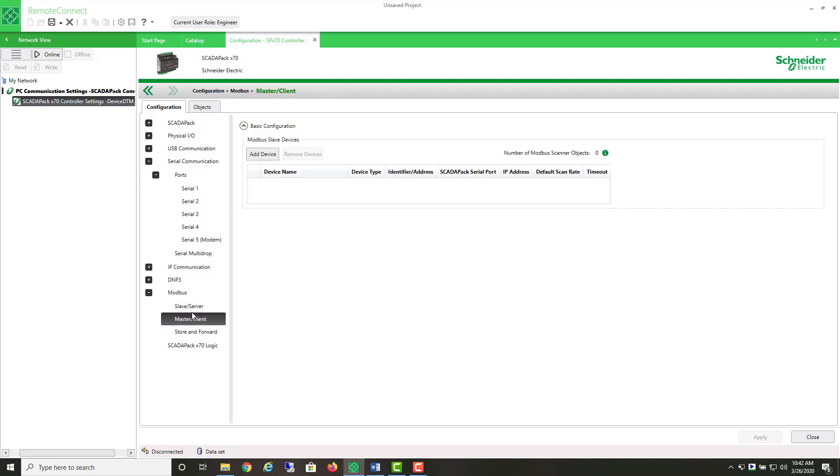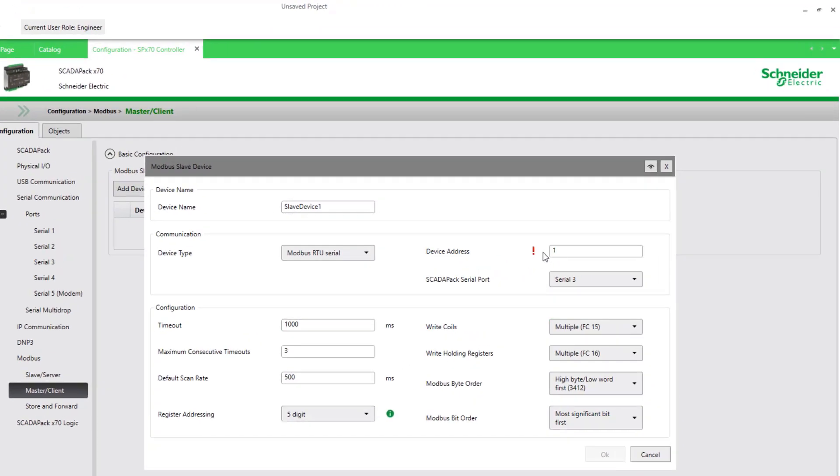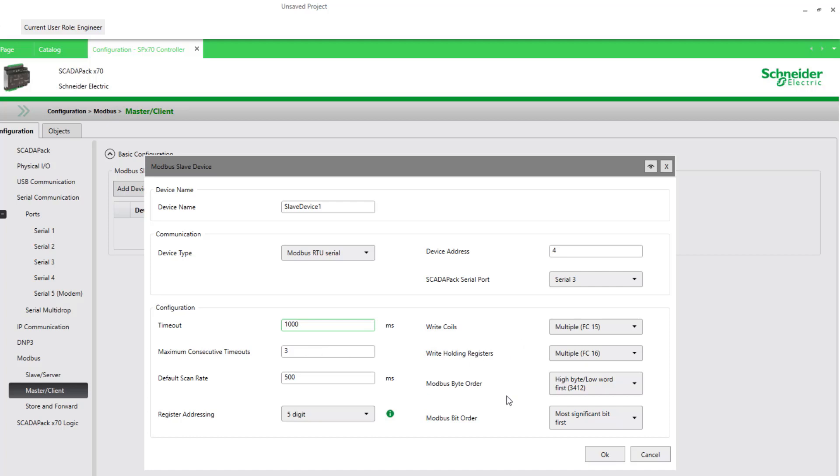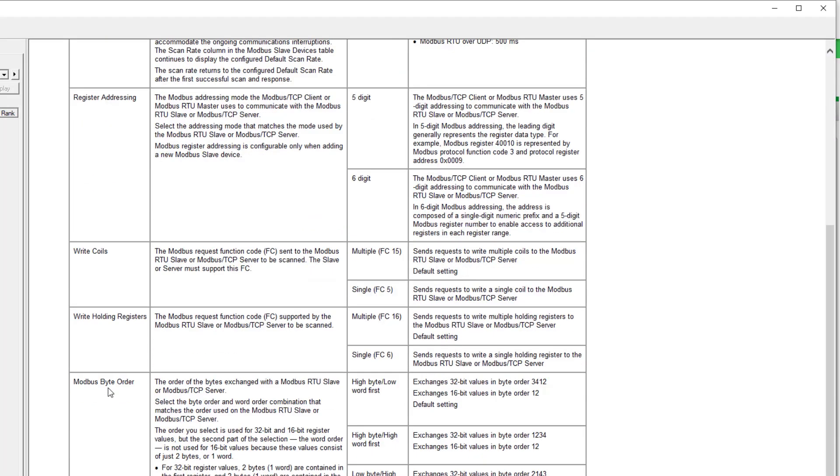However, I could have selected the Modbus protocol for any of the five serial ports. My pressure transmitter is at station address 4. And then these parameters here, I'm going to keep as their default. I'm going to use five-digit Modbus addressing, and I'll poll it by default every half second. There's a timeout every second and three retries. Note that you can select F1 on any of these dialogs and get more help on some of the other parameters. Also, here we have the order of the bytes and bits. I'm talking to a transmitter that's using the default order, so that can be something you might need to consider when connecting to some other devices.